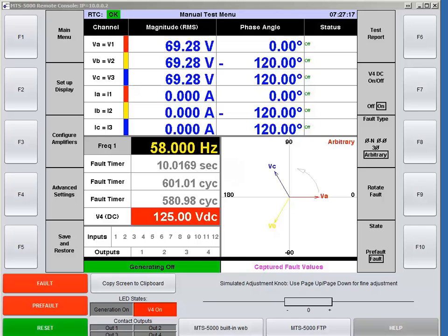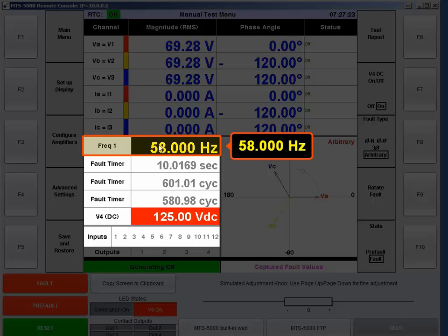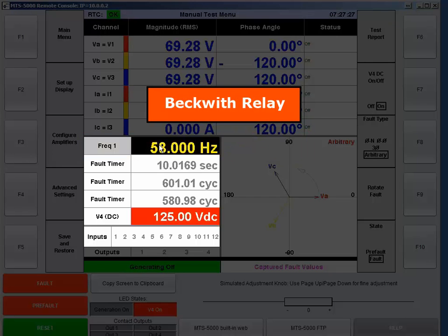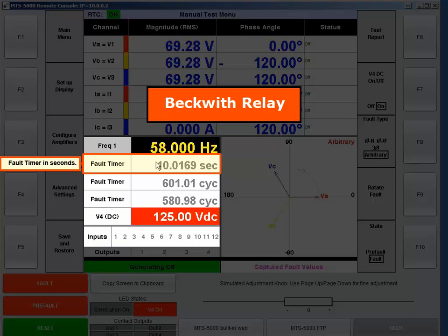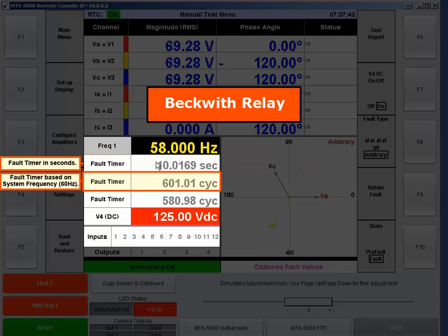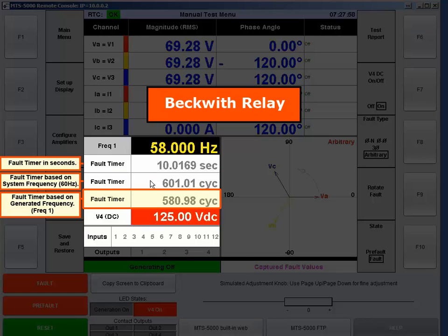Let's see that in action. I'm connected to the Beckwith relay and generating 58 Hz. The first timer is in seconds — that's how long the relay takes to operate, which in my previous test came out to 10.0169 seconds. The fault timer beneath that is in cycles based on the system frequency of 60 Hz, reading 601.01 cycles. The third timer is the fault timer in cycles based on the frequency I'm generating.